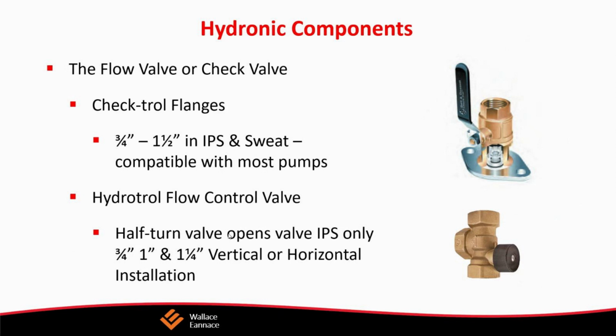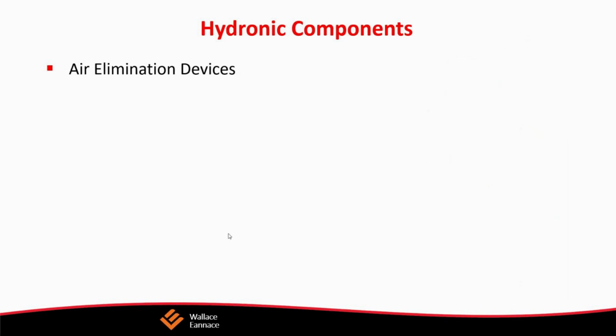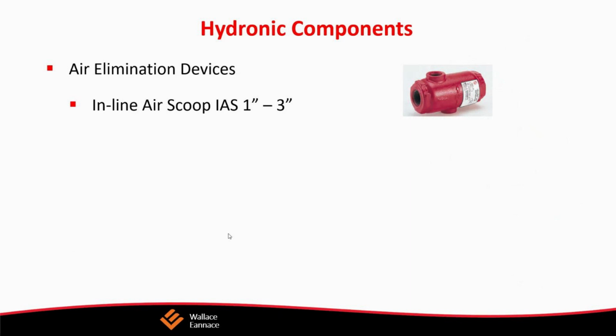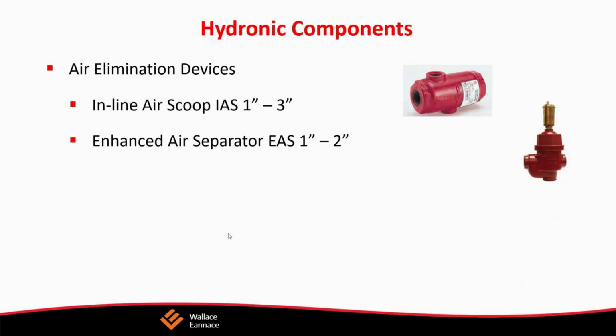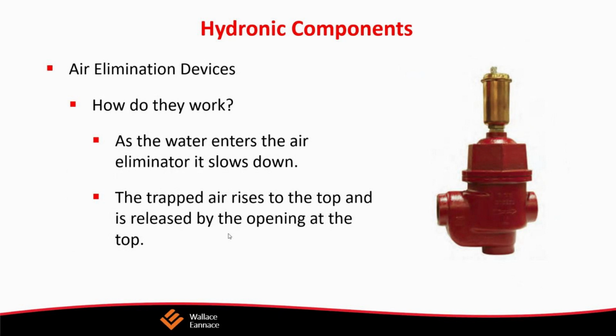This can cause overheating of zones that are off. What will happen is if we don't have any flow control valves, the gravity or ghost flow when we're heating one zone can switch over to another zone. Or for example, in the summertime, if you have an indirect fired water heater on your boiler, the ghost flow can actually send the water into the regular heating system. So gravity flow can occur in two pipes, and the return can actually be hotter than the supply. So that's why we put in a flow check valve. Otherwise you can have this reverse flow going in there. The flow check prevents that from happening.